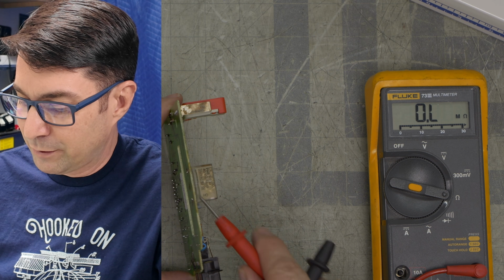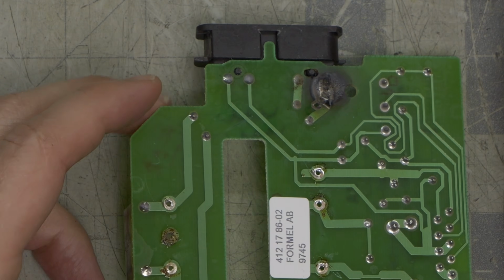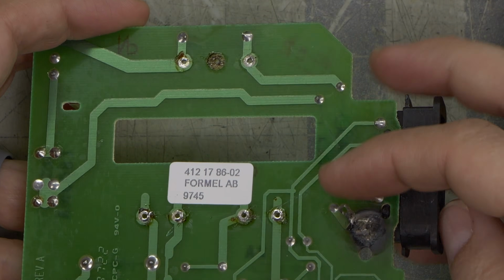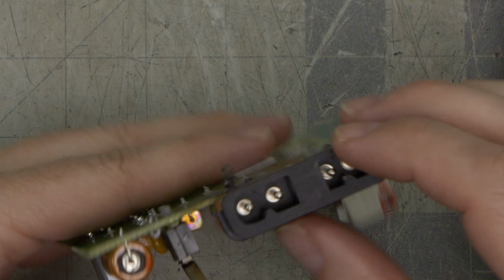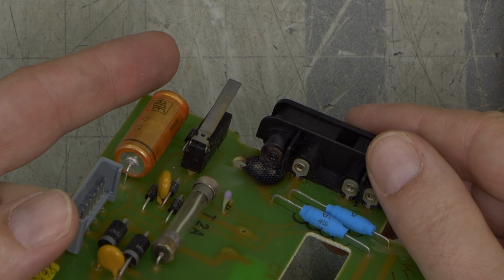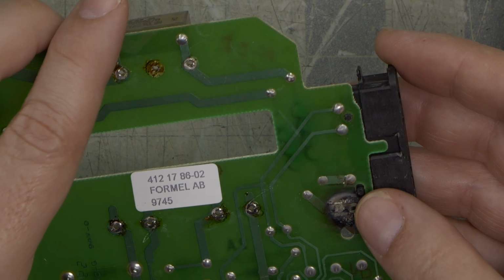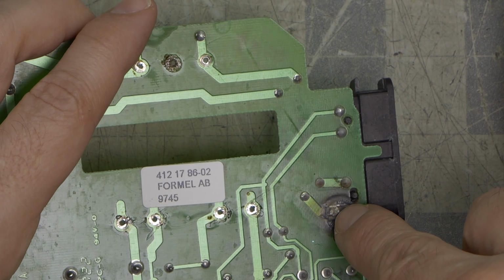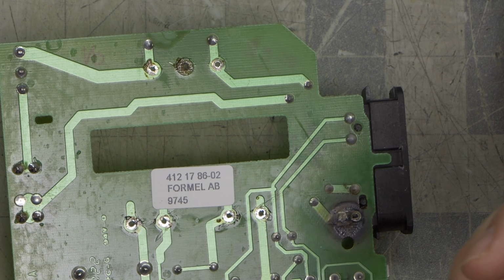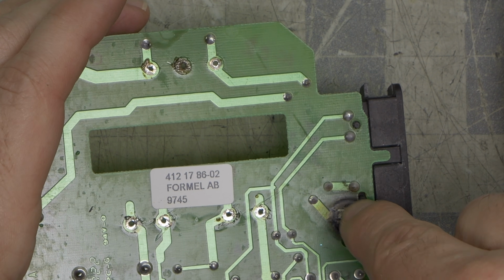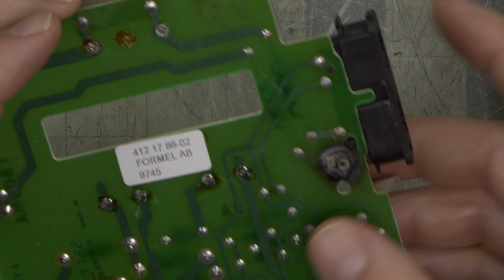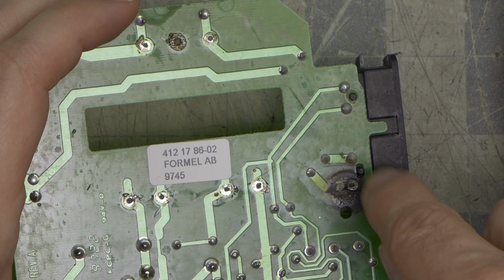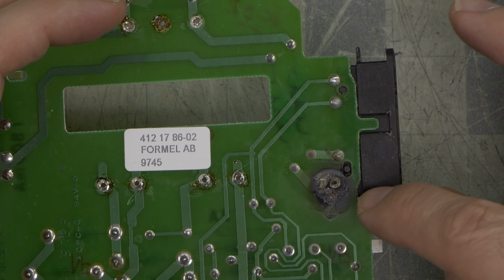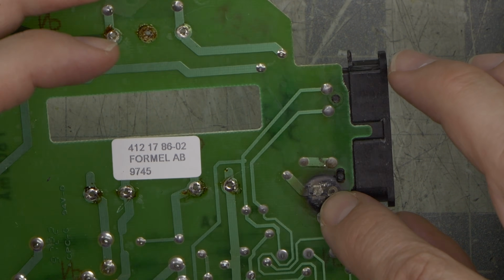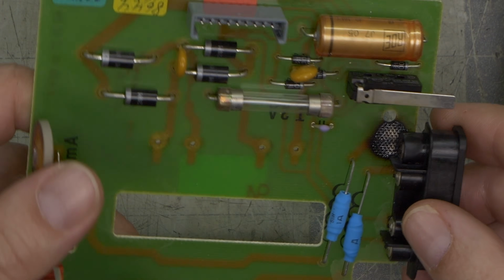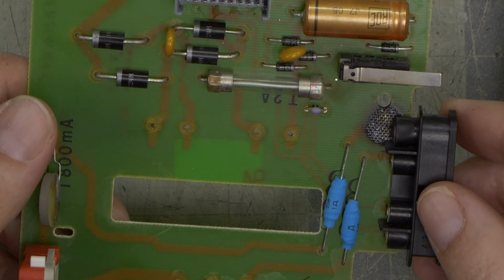So we said we're going to remove this anyway, that's one thing we're going to do. So far everything I'm checking here is looking good, except for this guy right here. The connector looks fine, but I think we had a bad solder joint right there. When your solder gets bad, you get high resistance, which causes heat buildup, which melts more solder out of the way, so you get more heat, and it runs away like that and creates this situation. Because your current flow was right here, and all that heat was right here, it wasn't actually going through the machine, so none of the protective devices blew.